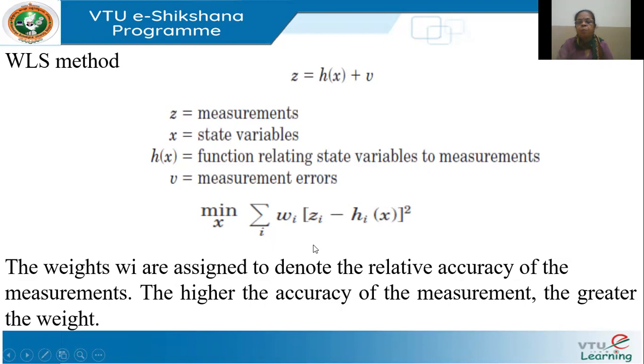So this is very popularly used in estimating power quality voltages. For example, a sag occurs at a point in a feeder, right? Using this sag value, I make an estimate of what would be the sag further downstream on the feeder, where I have not put a monitoring instrument. I may have the sag at the substation, and there may be four feeders going out from the substation. If I know the sag at the substation, I try to make an estimate of what would be the sag at the end of the feeders. So this is the meaning of estimate.